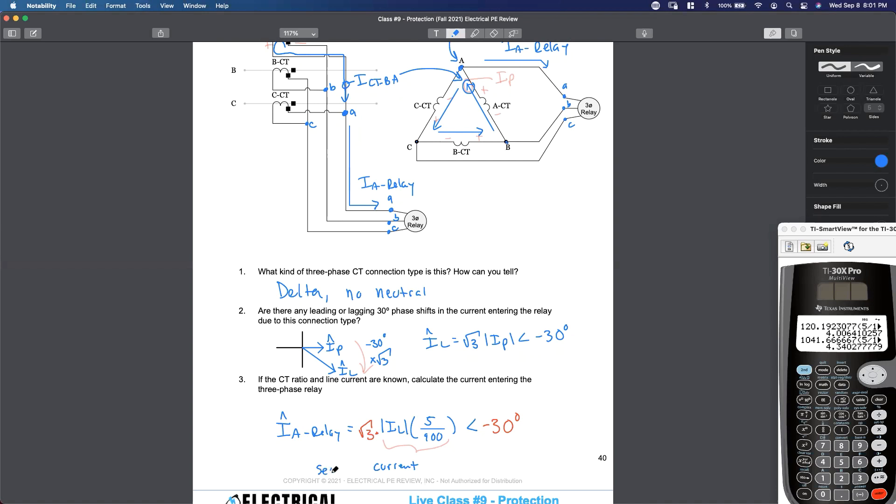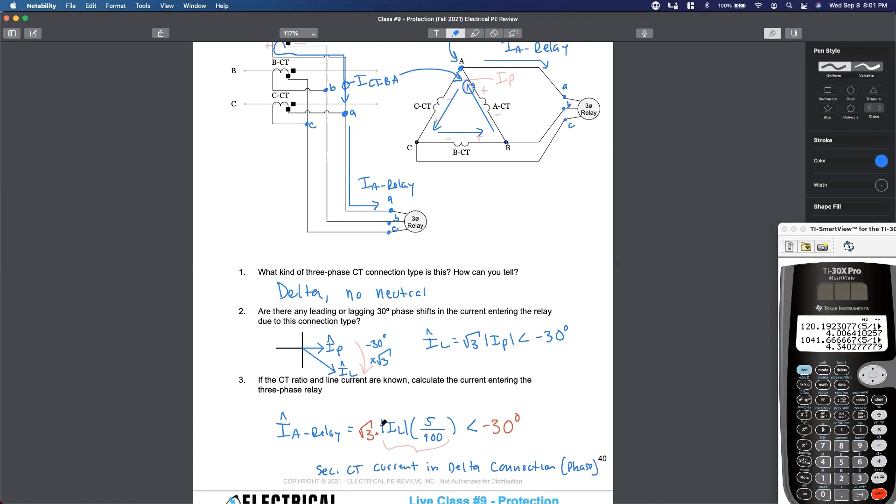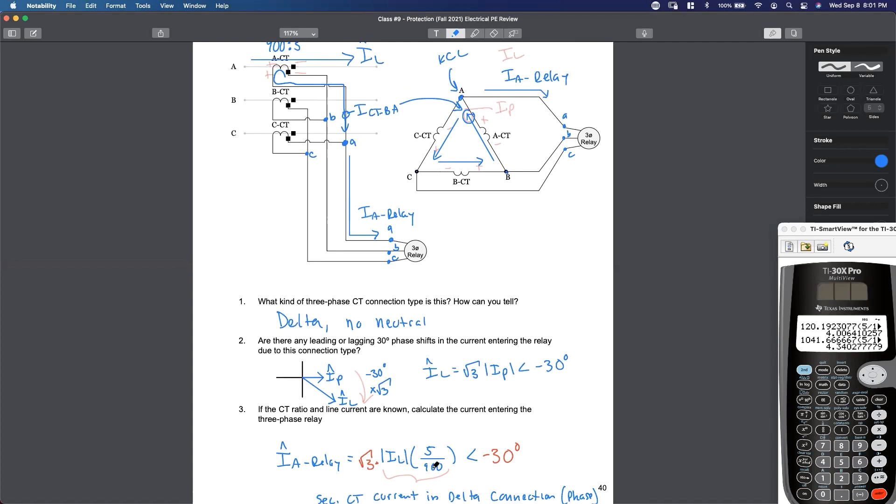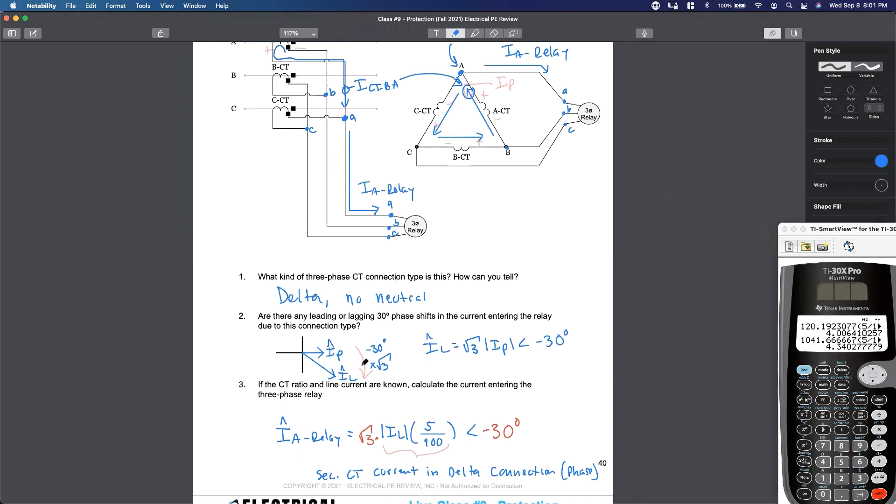This right here is the current, the secondary CT current in the delta connection phase. I line, step down by 5 to 900, is this current from B to A. To leave the delta, we've got to multiply by the square root of three, right? Here's the phase current on the secondary of the CT inside the delta. To leave the delta, it gets bigger by the factor of the square root of three, and then it lags by 30 degrees. It's just your delta relationships. Does that make sense?